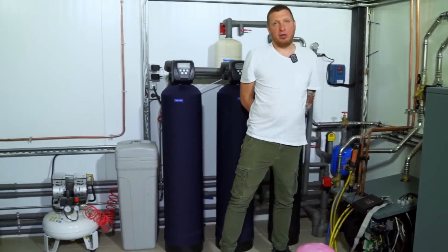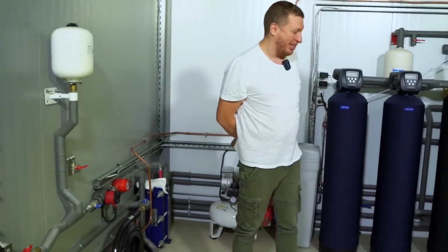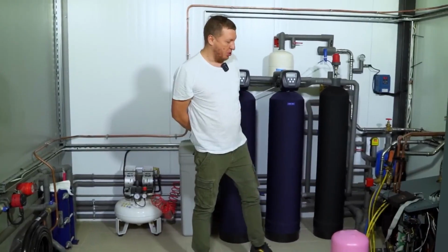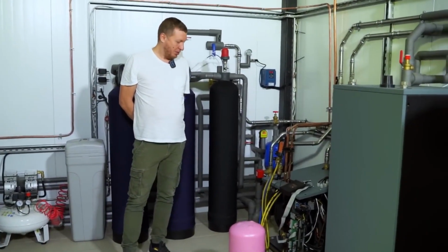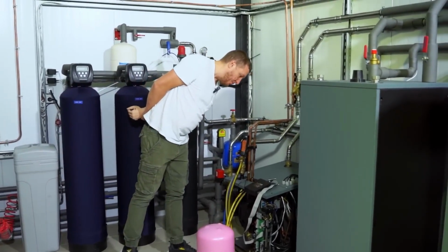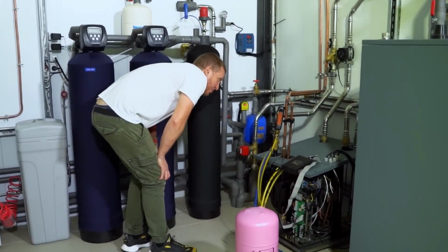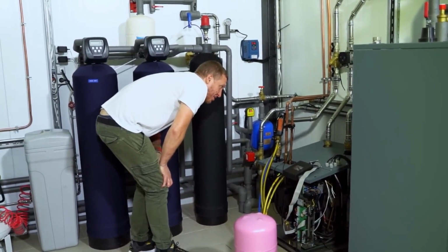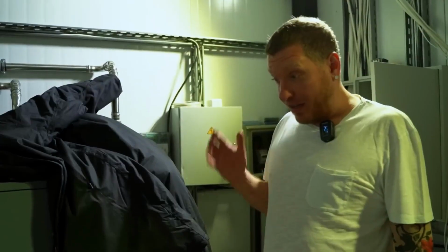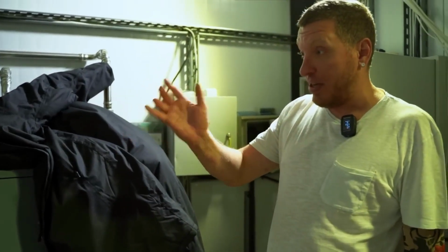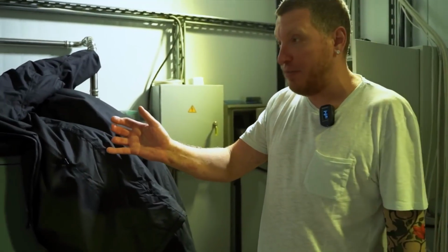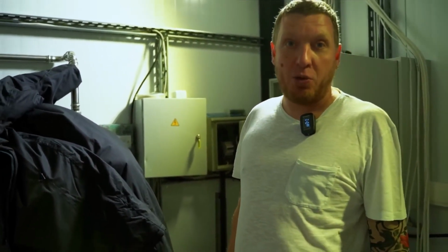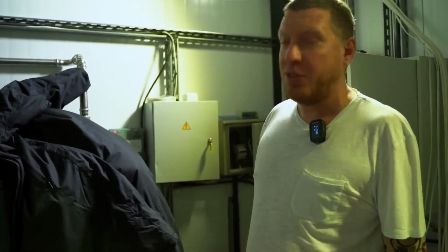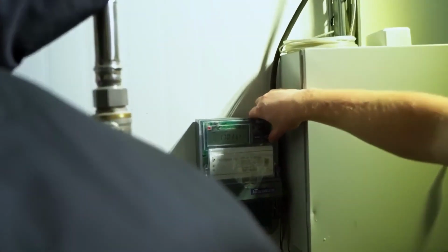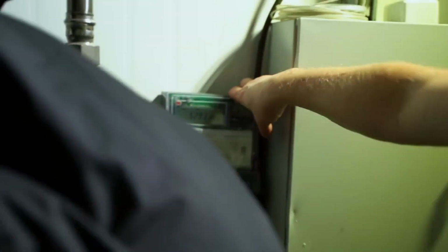Right now, it was running at 30 revolutions per second. Now it'll go up to 90 revolutions per second. And that's about 5,500 RPM, something like that. I wanted to talk about the power consumption. So the compressor, the heat pump is running at full power. Right now it's producing about 27 to 30 kilowatts of heat, because the condensation is low and the COP is really good. And it's consuming 5.2 kilowatts across all phases. There you go. So that's actually pretty good.